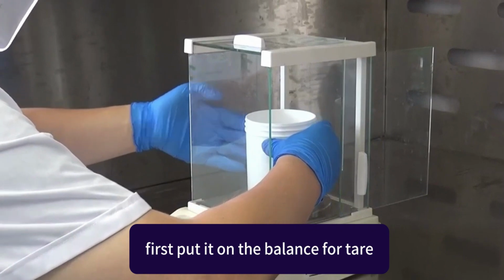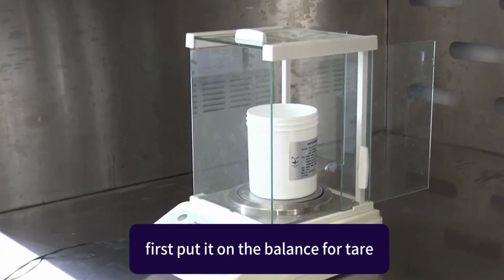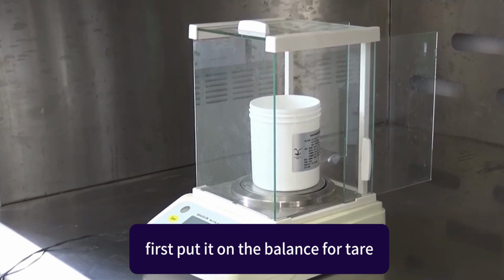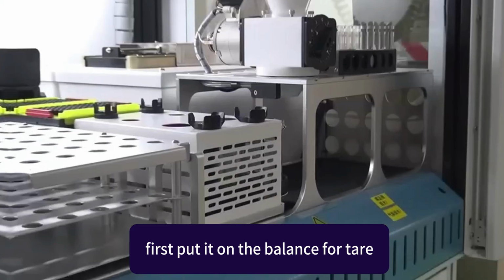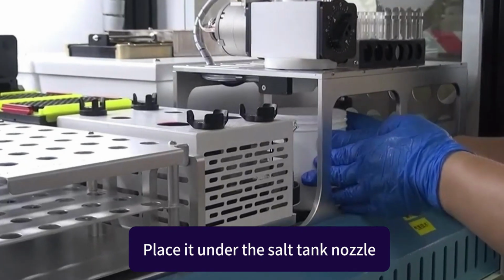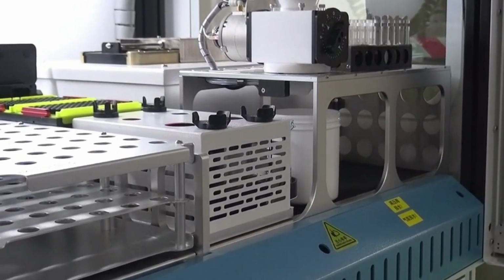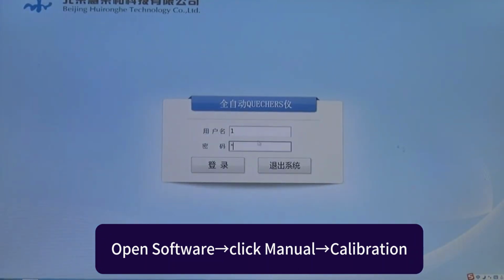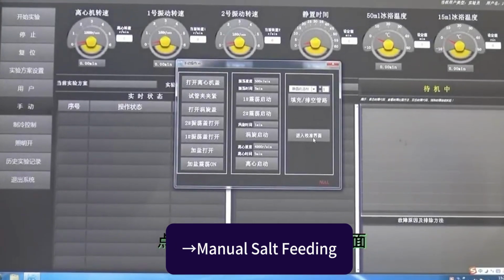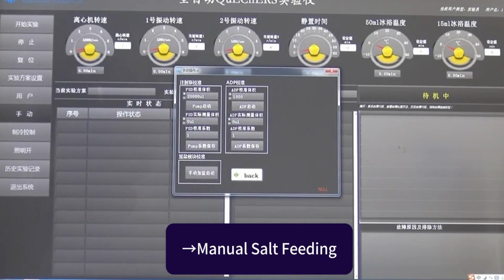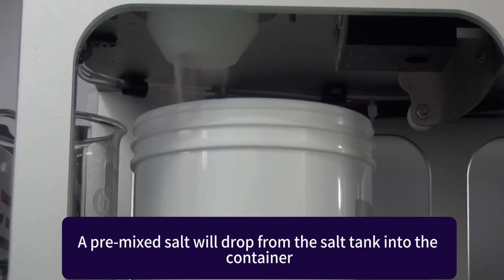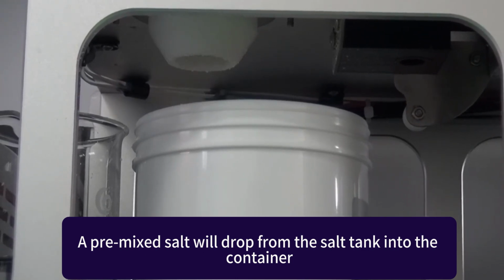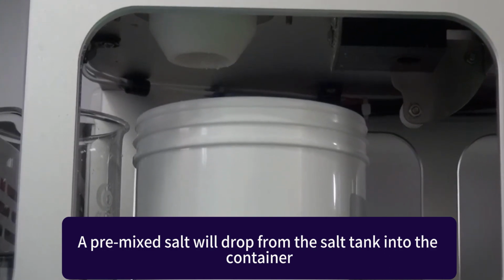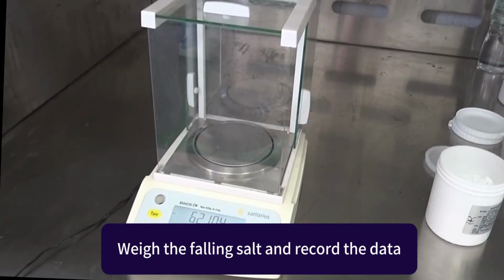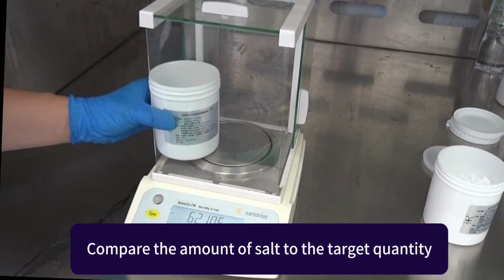Extraction salt calibration. Take a clean container. First put it on the balance for tare. Place it under the salt tank nozzle. Open software. Click Manual, Calibration, and Manual Salt Feeding. A pre-mixed salt will drop from the salt tank into the container. Weigh the falling salt and record the data. Compare the amount of salt to the target quantity.